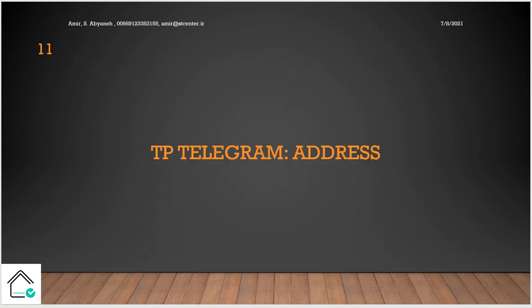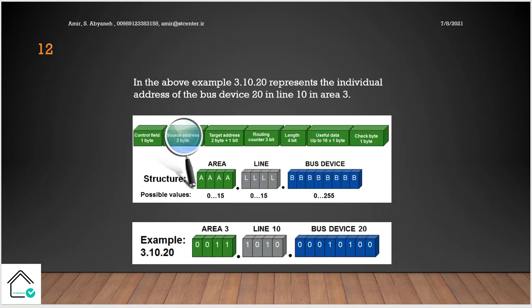TP telegram address. We want to talk about address, source address and destination address. The source address is the physical address of the sender. For example, the sender physical address is 3.10.20, so the source address is 3.10.20. That means the device is located in the area number 3, line number 10, and it's the 20th device.